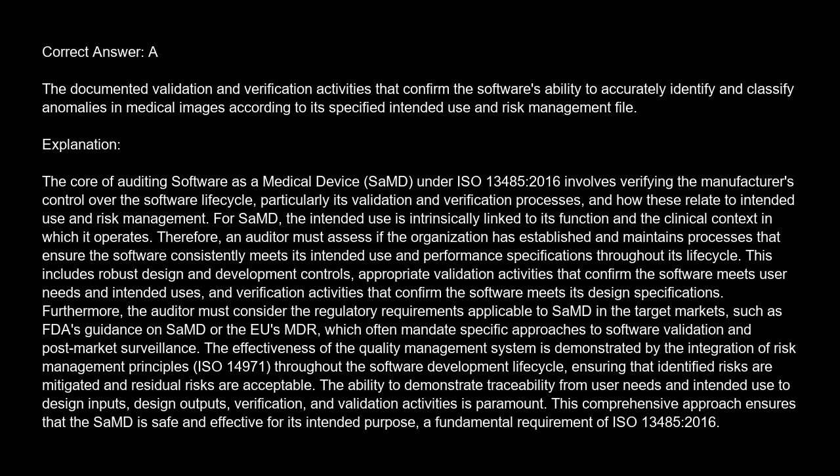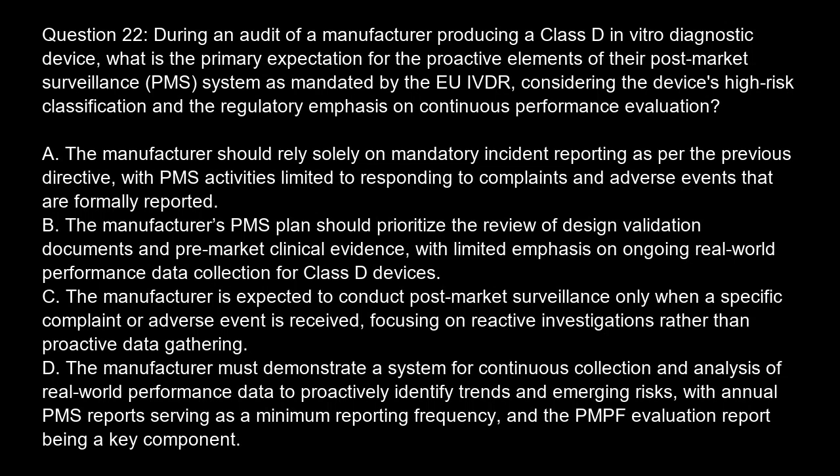The ability to demonstrate traceability from user needs and intended use to design inputs, design outputs, verification and validation activities is paramount. This comprehensive approach ensures that the SaMD is safe and effective for its intended purpose, a fundamental requirement of ISO 13485:2016.